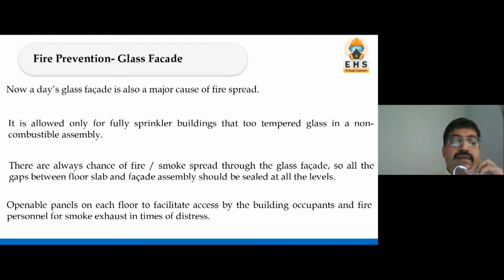The second point is the chances of fire spreading through the glass facade. Since this facade is outside the building, fire and smoke can travel directly using it. So similar to the shaft, every floor's facade should be sealed so there is no vertical fire spread. Also, openable panels are required for glass facades.